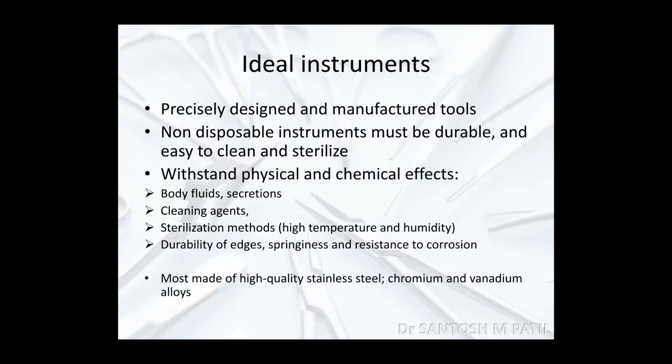Before understanding a surgical instrument, one should know the particular features a surgical instrument should have — what we call an ideal instrument. These instruments are precisely designed and manufactured tools, and most non-disposable surgical instruments must be durable and easy to clean and sterilize. All surgical instruments should withstand physical and chemical effects of body fluids, secretions, cleaning agents, sterilization methods, high temperature and humidity. One instrument should have durability of edges, sustainable springiness, and resistance to corrosion.